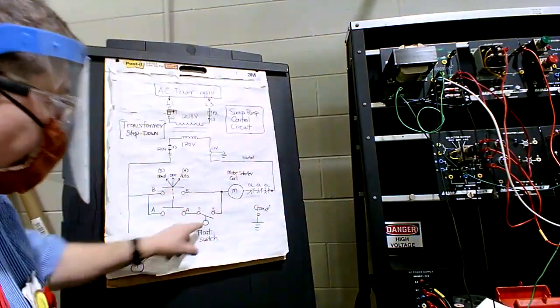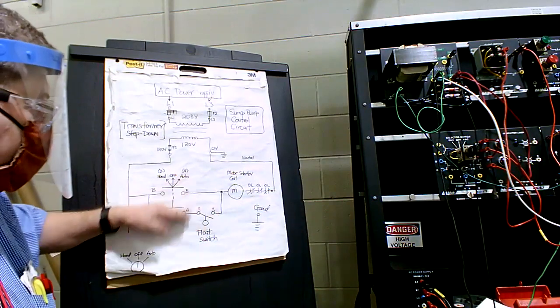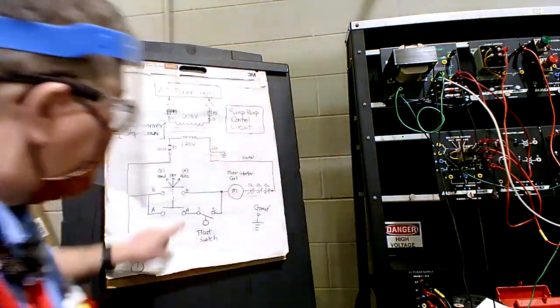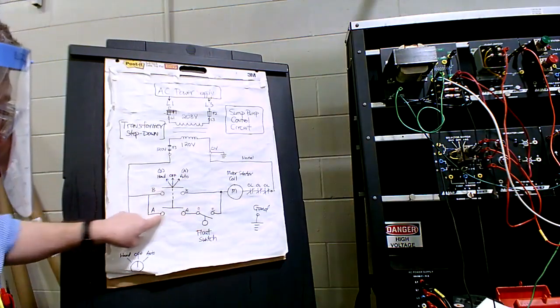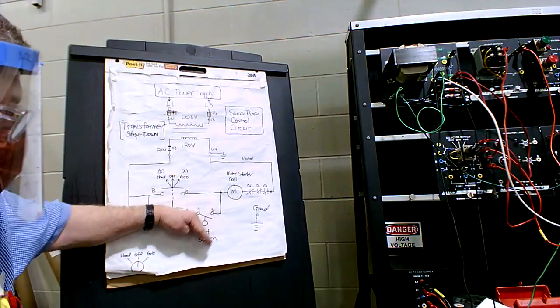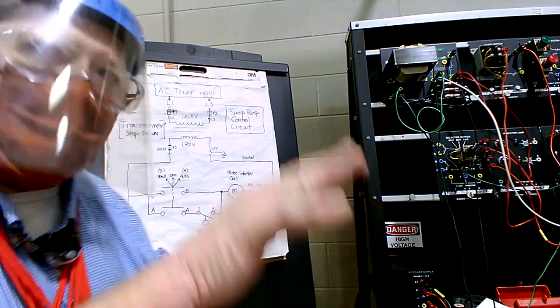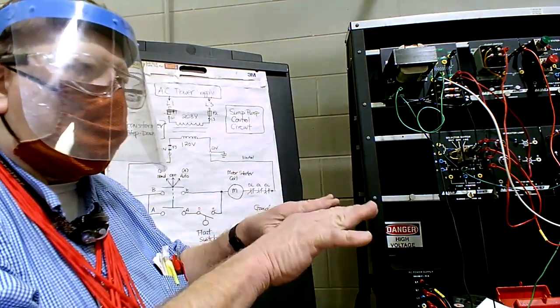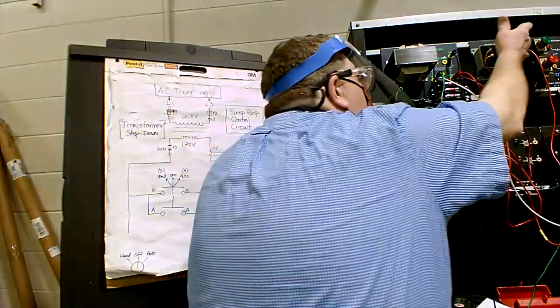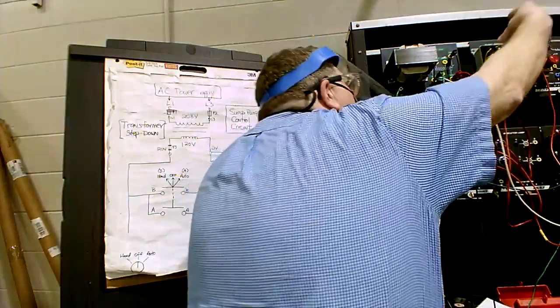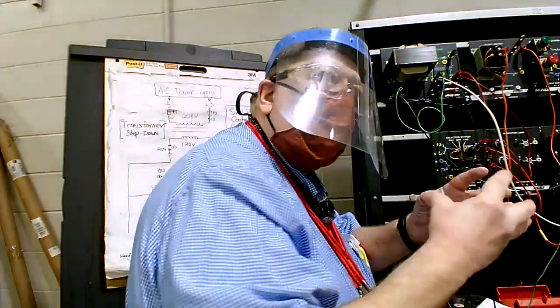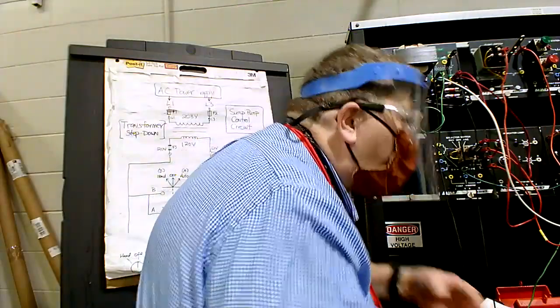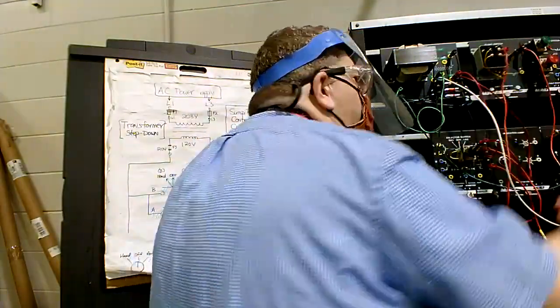You're basically disabling the whole circuit there by putting it into the off position. Now you go to auto, and then it opens this one and closes this one, and then the float does it automatically. As the water rises in the pit, it's going to cut the pump on, and there'll be a ball float tied to this, like in your toilet. If the ball goes down and the water goes down, it's going to cut the pump off. So it'll run automatically that way.